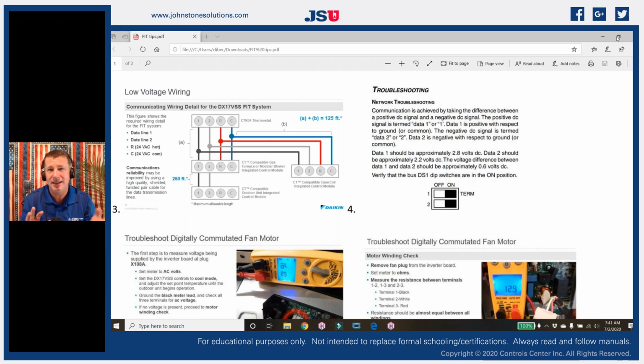It's typically going to be like 2.5 to 3 volts, somewhere in that ballpark. It's about half of that 5-volt DC signal. Then if we go from ground or common to number 2, we're going to see the inverse of that. We're going to see a negative DC signal because it's sending out on number 1 and coming back on number 2, so we have a polarity difference. What we look for is a differential between those. It's called a DC voltage bias.